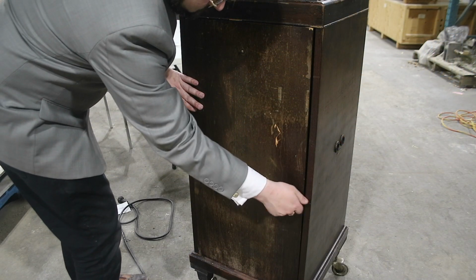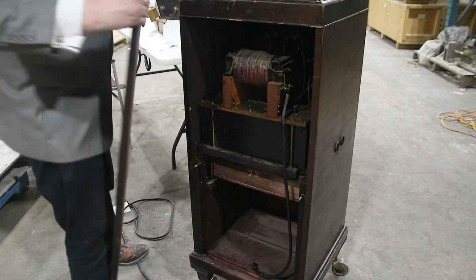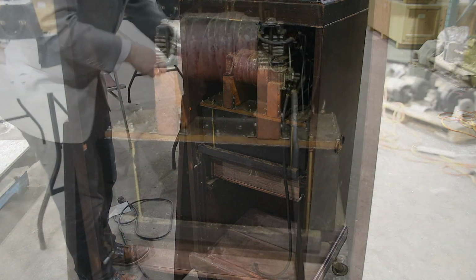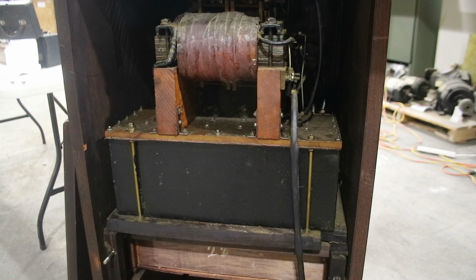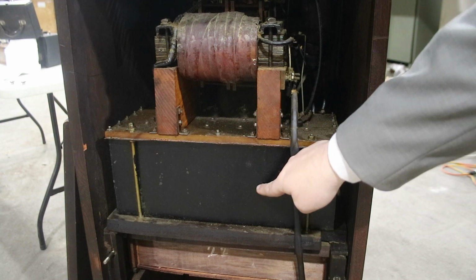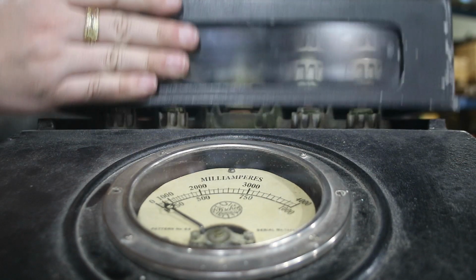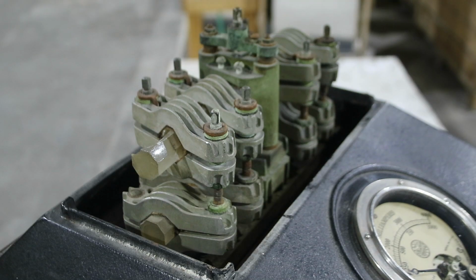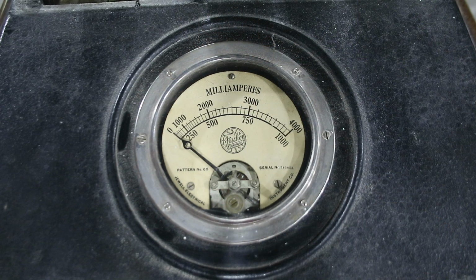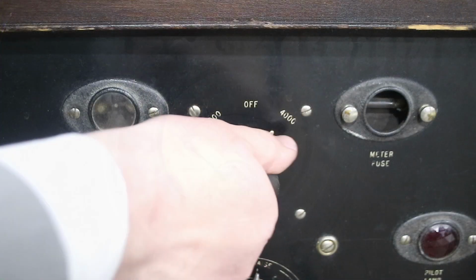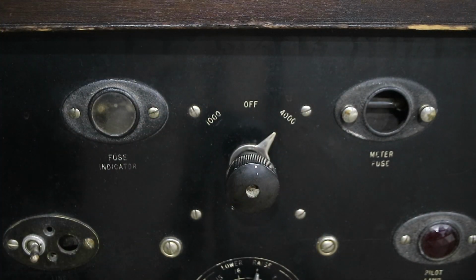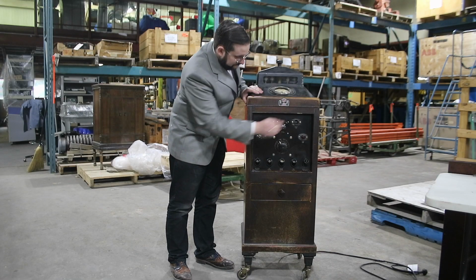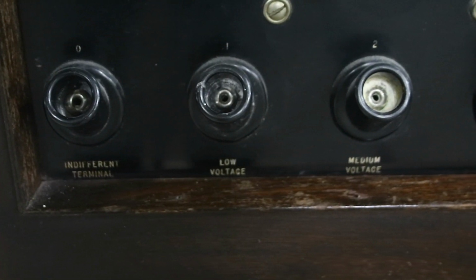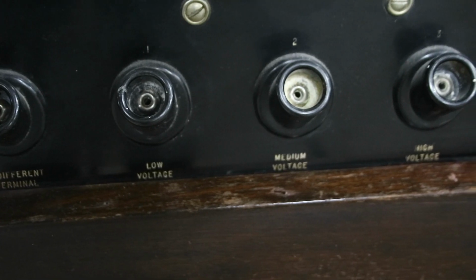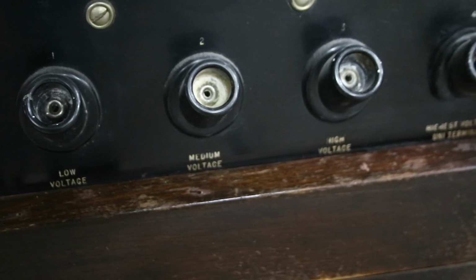And if we look inside, we'll see that this is the exact same mechanism as the earlier medical coils. So here we have our iron core primary transformer, which provides high voltage AC electricity to the circuit. We have our big capacitor bank. And then at the top here, behind this window, we have our row of spark gaps for exciting the circuit. Other controls here, we have our master ammeter here. We have our selector switch for the range of the ammeter, either one scale or the other. We have a pair of fuses. We have our on-off switch. We have our power selector dial. And then we have a number of terminals for attaching our accessories, which go from the indifferent terminal all the way up to our highest voltage.